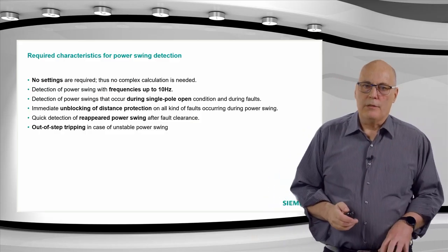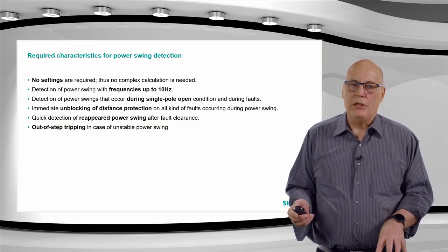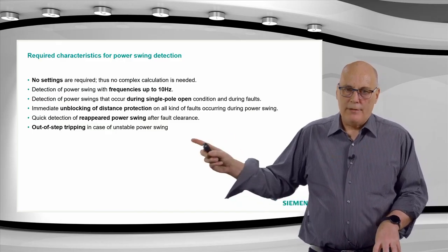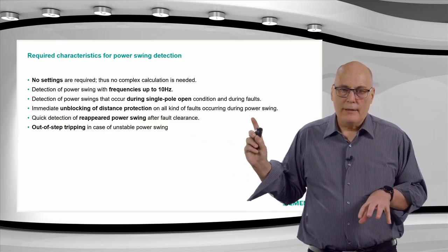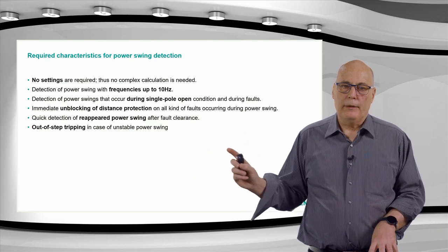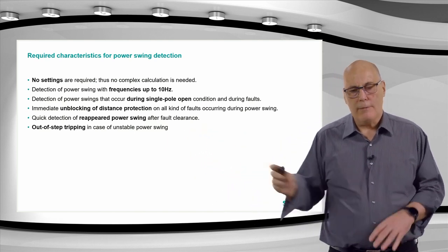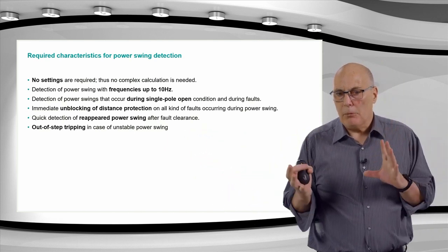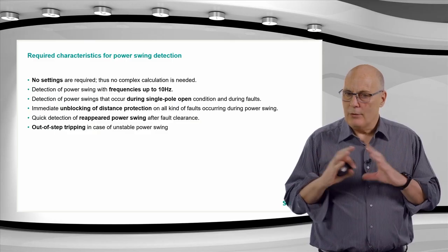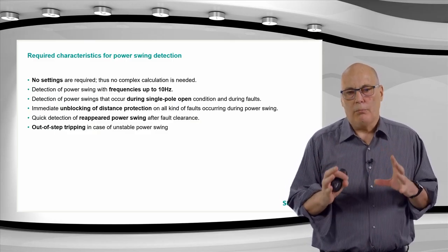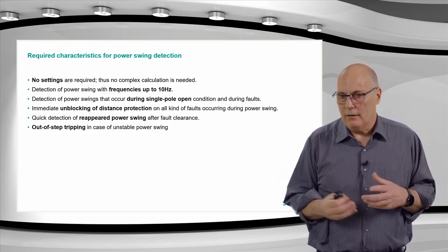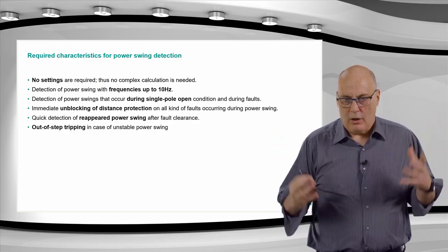We'll look at these conditions later on. So this is just some features of the power swing blocking. Out-of-step protection in SIPROTEC 5 is a separate function that you would use if you want out-of-step protection. It's the same principle behind it, but it's a different thing. It's not distance protection. It's a function that you apply to recover from, say, a disaster, one can call it.